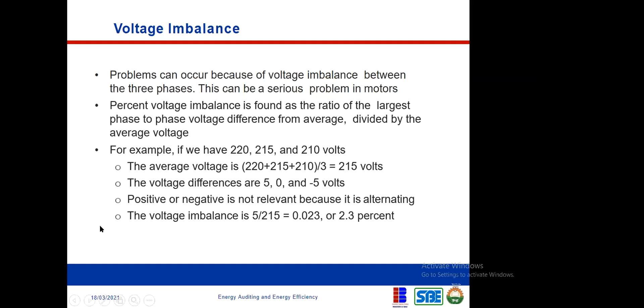Let's have a further example. If we have 400, 385, 409 on a three-phase board, the voltage imbalance is the maximum deviation from the average divided by the average voltage. Remember, this is the definition of how you determine voltage imbalance. So the maximum deviation we have there is 13.